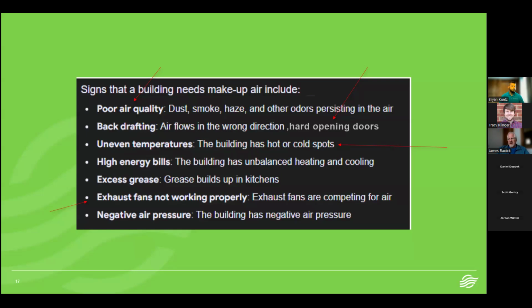How bad does it get? The worse negative a building gets, the more uncomfortable it gets, the more you're going to have a hot core in the middle of the building trying to keep the perimeter miserable, or you're going to have to use some other types of radiant heat to try and put a band-aid on what really needs to be a positive pressurized space. High energy bills, it's unbalanced heating and cooling. Cold air comes in, it displaces warm air near the floor that your heating system is producing and pushes it up to the ceiling, doing anybody good, it just costs money to heat that air.